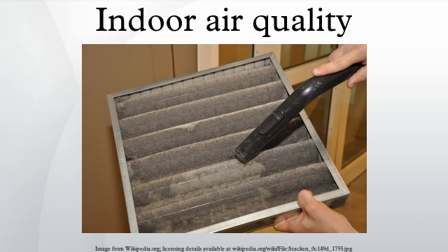In classrooms, the requirements in ASHRAE Standard 62.1, Ventilation for Acceptable Indoor Air Quality, would typically result in about 3 air changes per hour, depending on the occupant density. Of course, the occupants aren't the only source of pollutants, so outdoor air ventilation may need to be higher when unusual or strong sources of pollution exist indoors. When outdoor air is polluted, then bringing in more outdoor air can actually worsen the overall quality of the indoor air and exacerbate some occupant symptoms related to outdoor air pollution. Generally, outdoor country air is better than indoor city air.